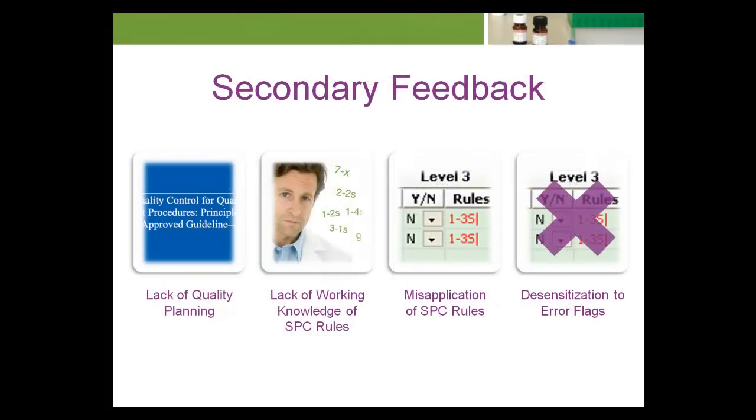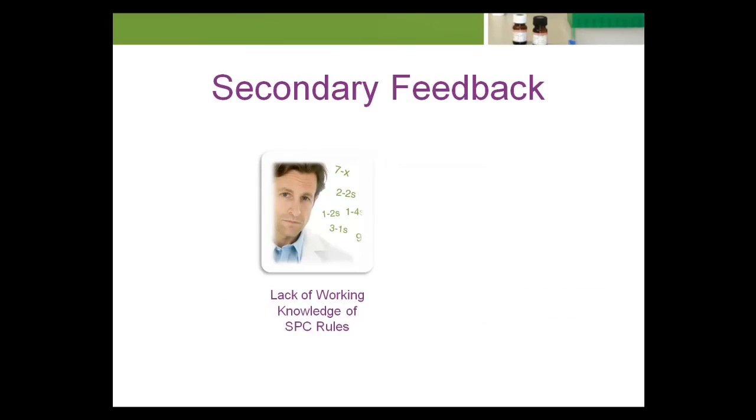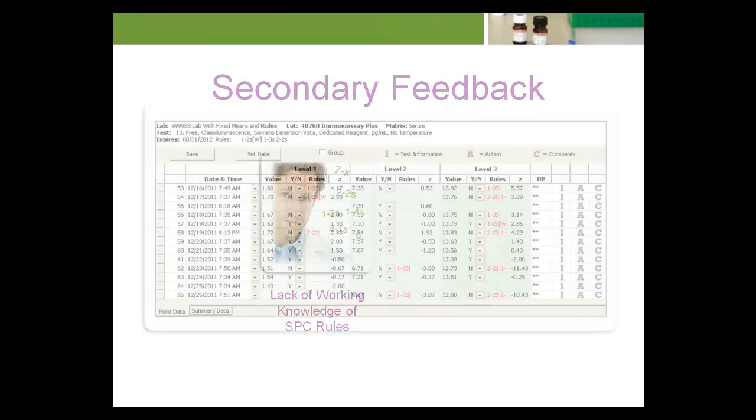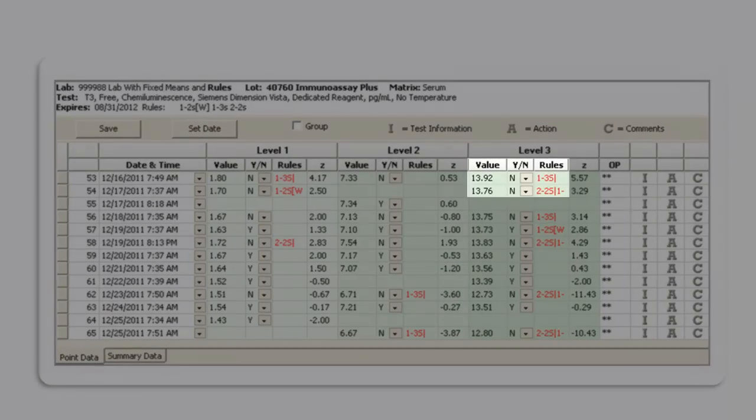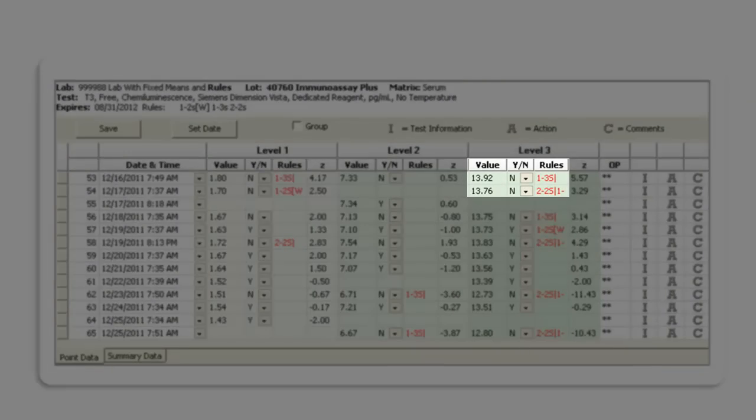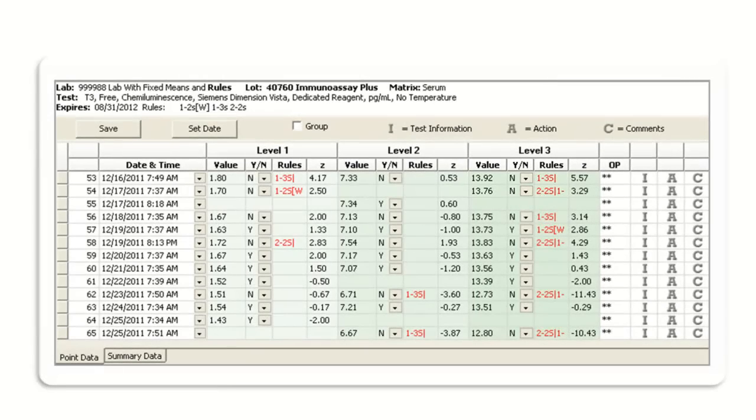Technologists are often not aware of the statistical power of each SPC rule when applied singly or in combination. Often they are also not aware that some rules identify error due to imprecision and others identify errors due to bias. Lack of a working knowledge of the SPC rules can lead to misapplication and an increase in false error flags. This results in rejection of credible patient test results that are appropriate for clinical decision making.